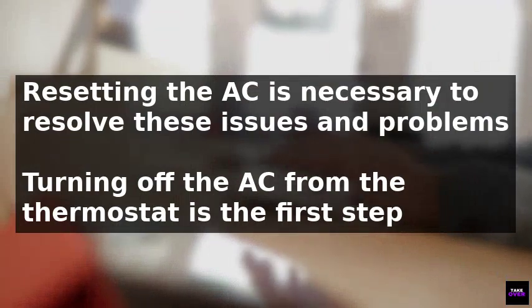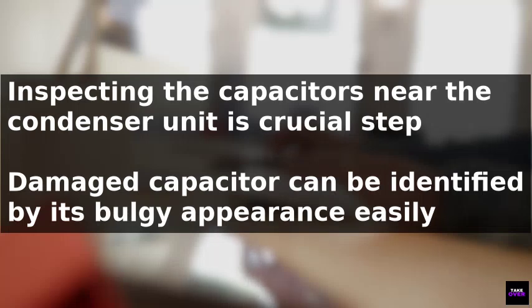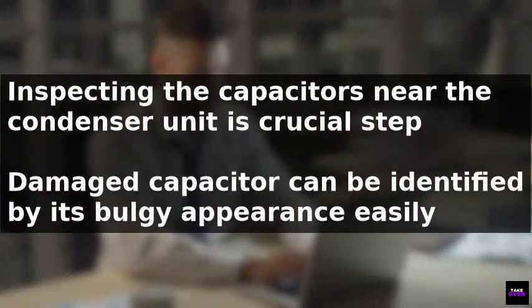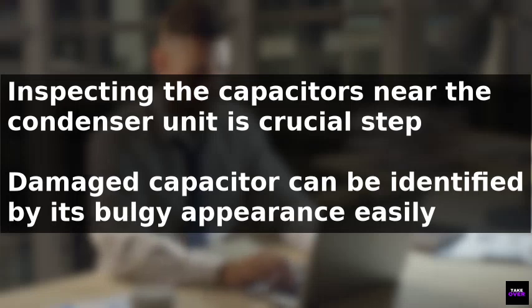If it is not, inspect the capacitors, which are usually located near the condenser unit. A damaged capacitor can be identified by its bulgy appearance. To discharge the capacitor, use a screwdriver with an insulated handle to short the terminals. Then replace the damaged capacitor and restore power to the unit.